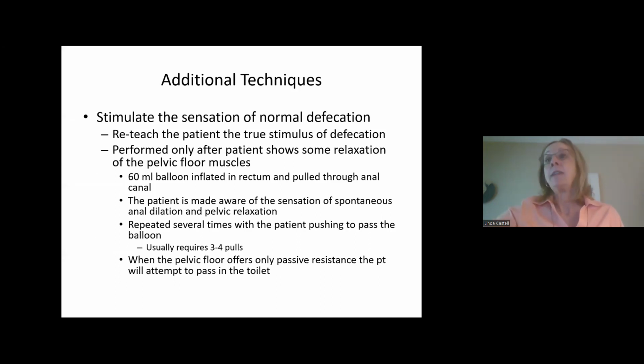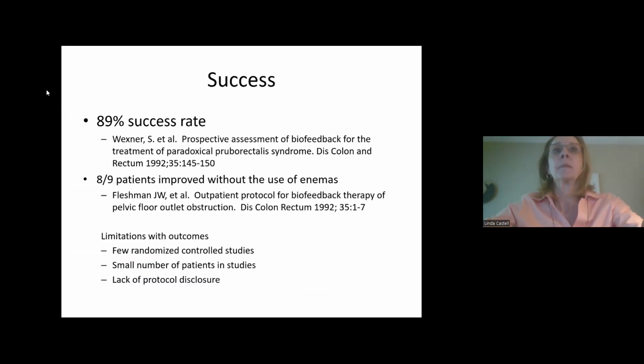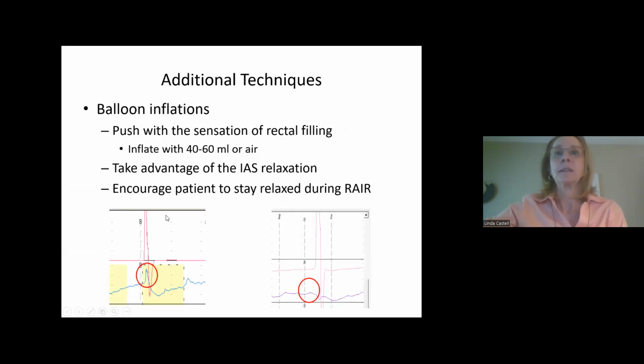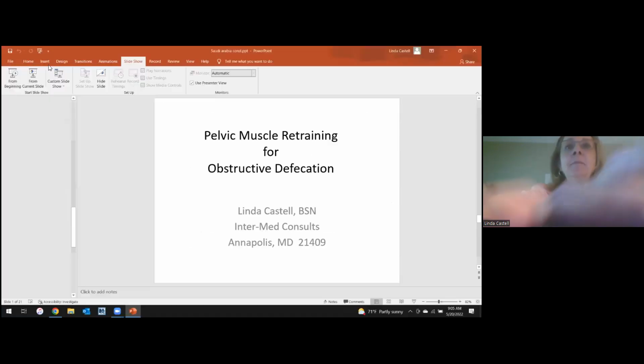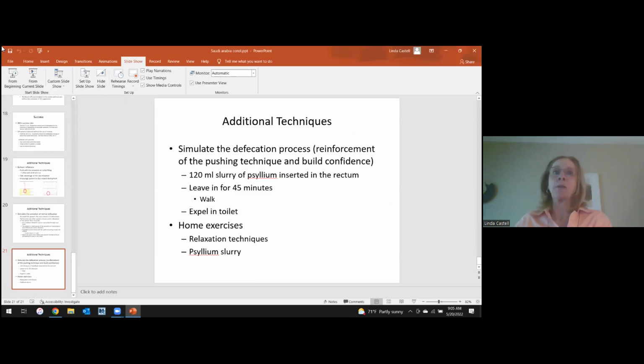The biofeedback program is with the EMG. It's similar to what I just showed you. You're going to have your 2 channels, and you're going to encourage your patients to set their threshold so that when they bear down, the EMG activity goes below the threshold. So instead of setting your threshold high, you're going to set it low, below baseline.